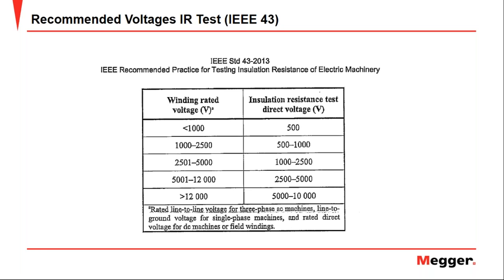So we measure the temperature in the case of the motor, but that is not the temperature of the winding. If the motor was running, we have to take the temperature reading on the casing of the motor and add about 10 degrees Celsius to know the real temperature of the winding. But as we said in the webinar, that is not in the standard. That is just a common practice, a rule of thumb.